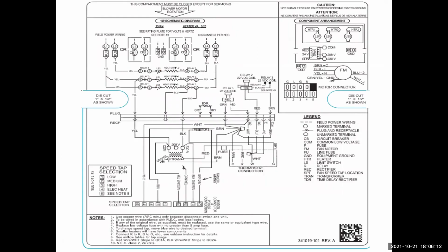Okay, here's kind of a main wiring diagram of your blower, your fan, and your heater package. Notice there's no Y connection on the fan terminal strip. The Y is wired directly to the outdoor unit. So it goes into the fan coil unit, you wire nut it, and you send it outside to your heat pump or your air conditioner.